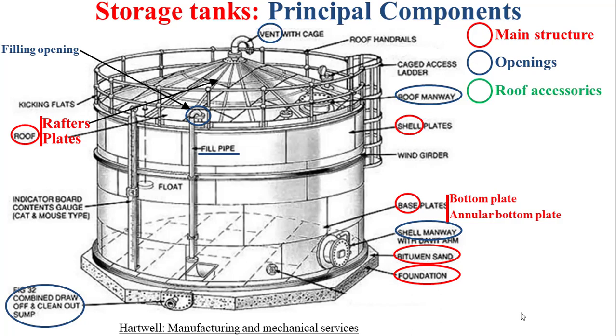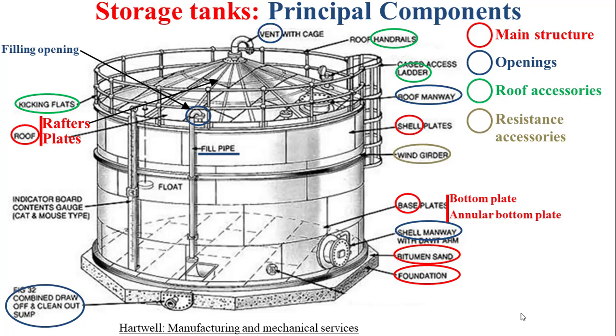For the roof we also have roof accessories. We have the ladder permitting access to the roof, and we have the handrails in association with the kicking plates to ensure the safety of workers when they are on the roof. The storage tanks also present resistance accessories such as the wind girder, permitting the storage tank to resist against wind load. They also present level indication accessories such as a float in association with an indicator board to indicate the level of the stored product within the tank.